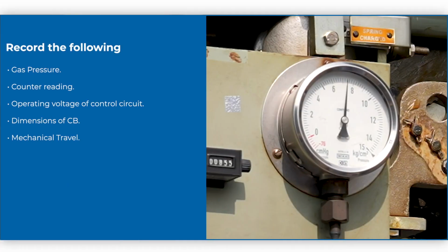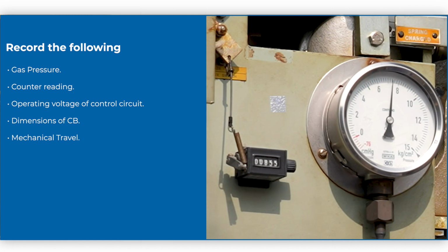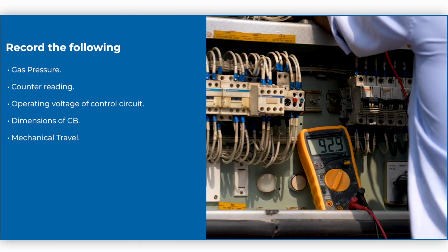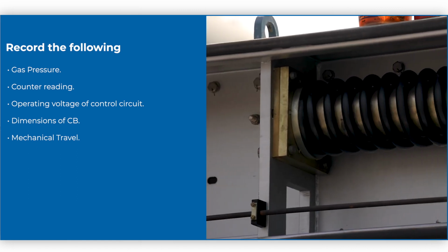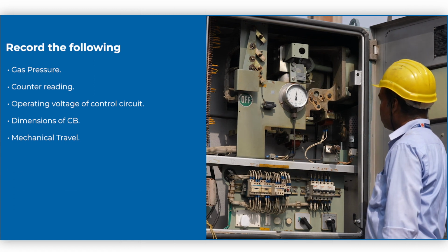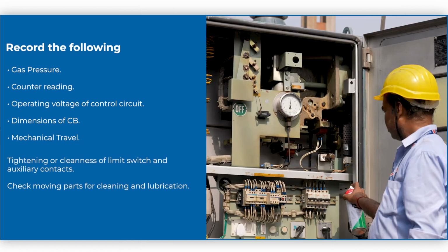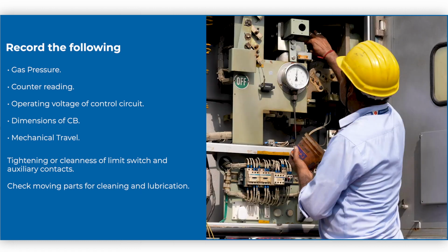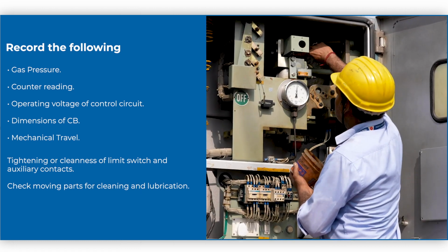Record the following: gas pressure, counter reading, operating voltage of control circuit, dimensions of CB, mechanical travel. Tightening or cleanness of limit switch and auxiliary contacts. Check moving parts for cleaning and lubrication.